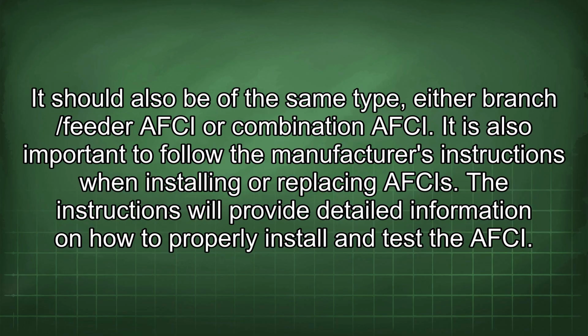It should also be of the same type, either branch/feeder AFCI or combination AFCI. It is also important to follow the manufacturer's instructions when installing or replacing AFCIs. The instructions will provide detailed information on how to properly install and test the AFCI.